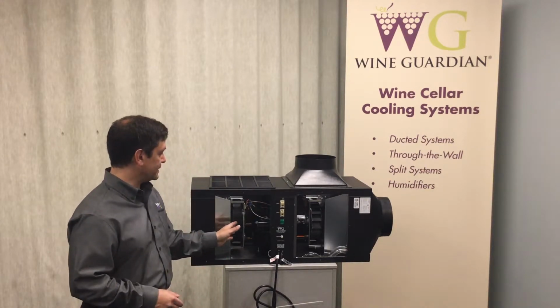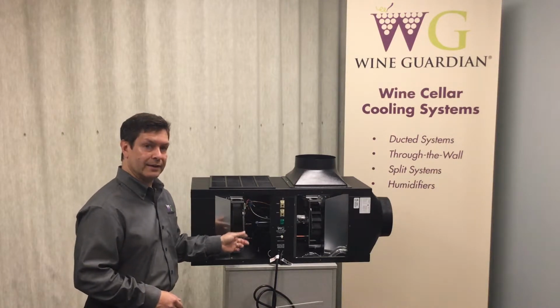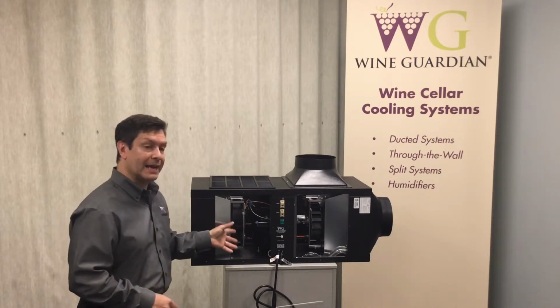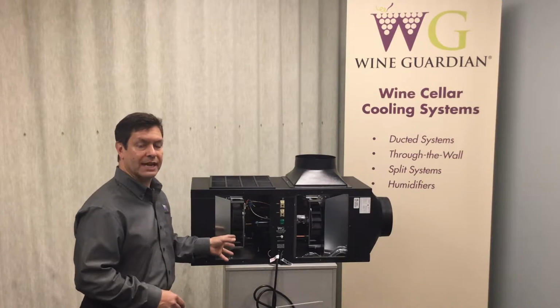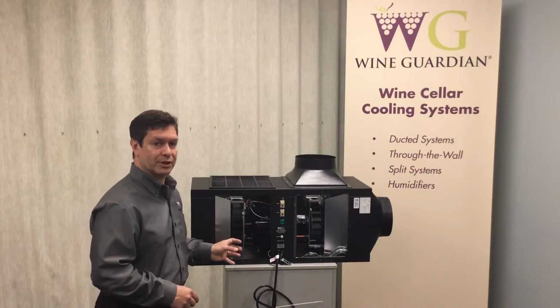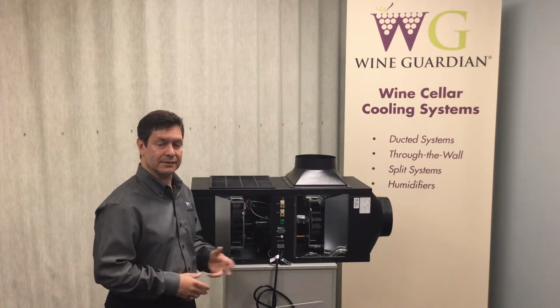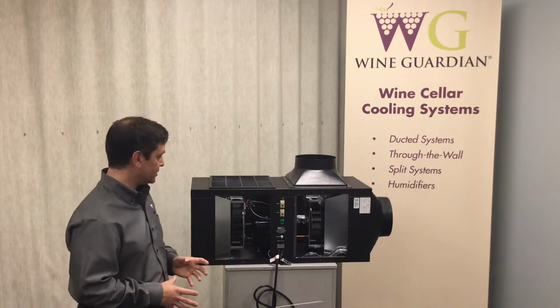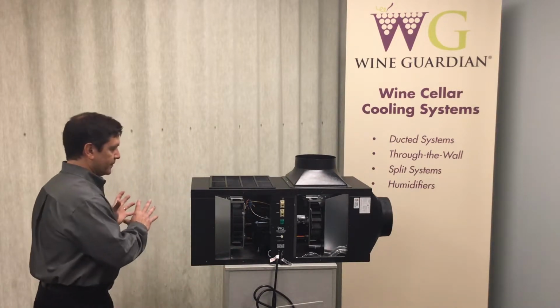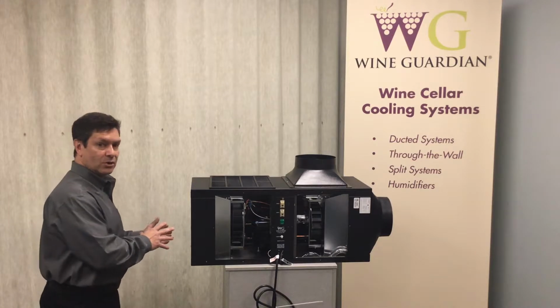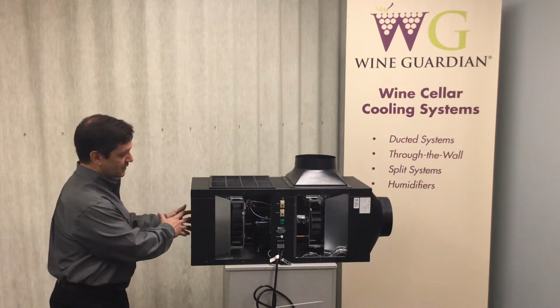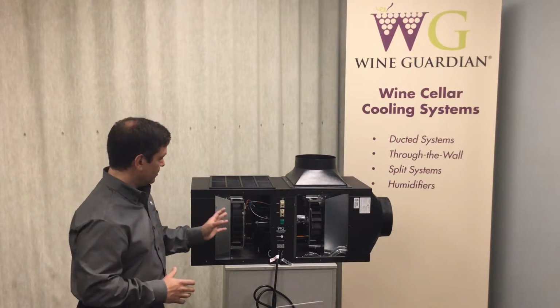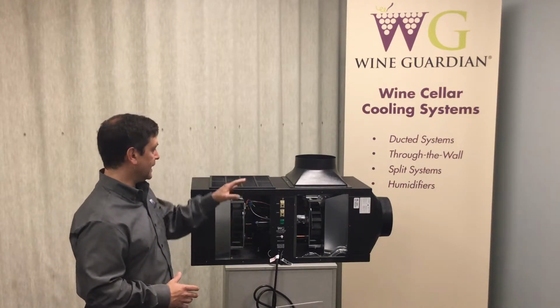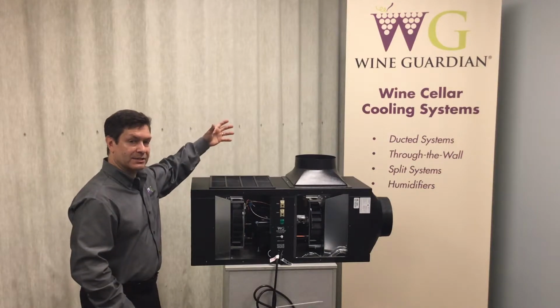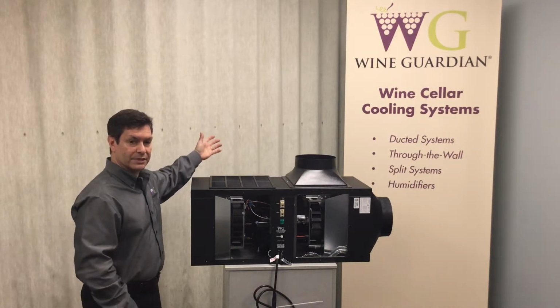The fan cycling switch acts to control the fan. This fan may not need to come on all the time to keep the refrigerant pressures where they need to be. Okay, the way that it works is if you have this mounted in a cold environment, air goes across the condensing coil through the fan and then maybe exhausted out into the space or exhausted out of the system.